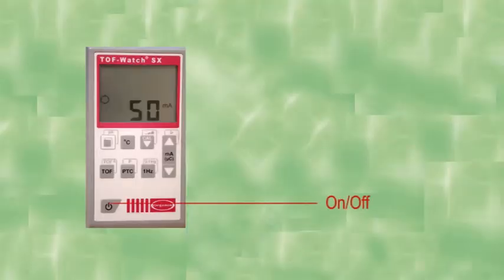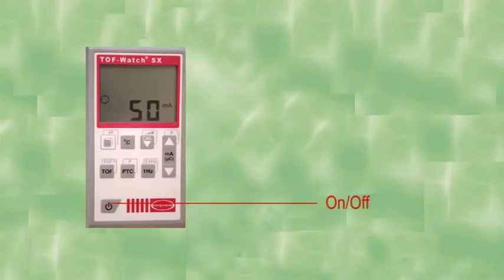The button here is the one which turns the monitor on or off. A short press on this button, which is about 1 second, stops whatever function is on play. For example, if TOF is being used, a press on this for a second will stop the TOF or clears the display. A long press of the same button puts the monitor off. In order to turn the monitor on, yet another long press on the button will switch the monitor on.